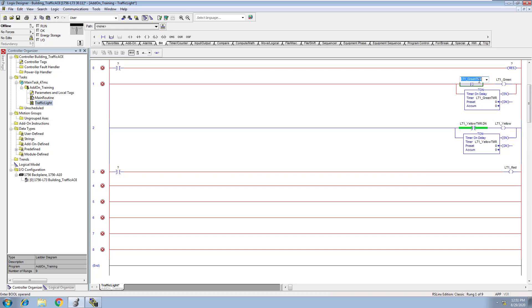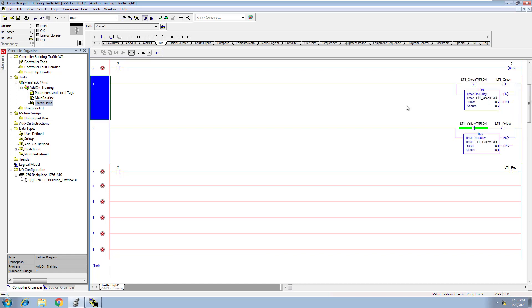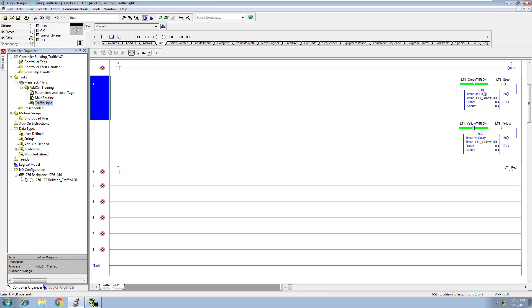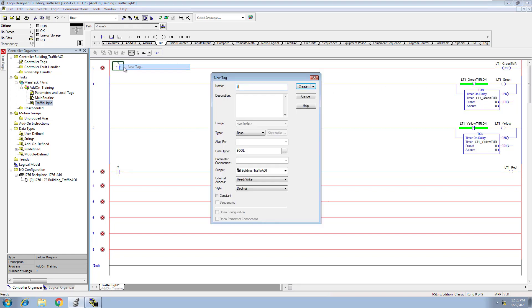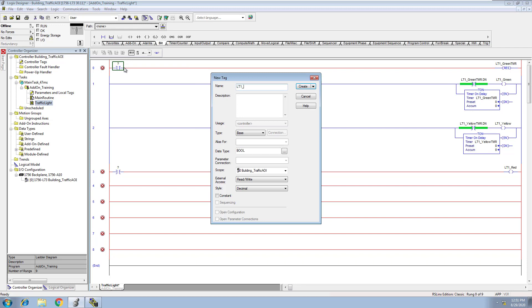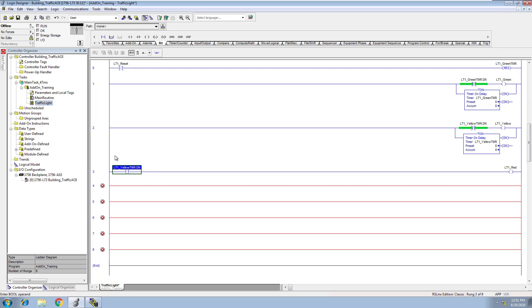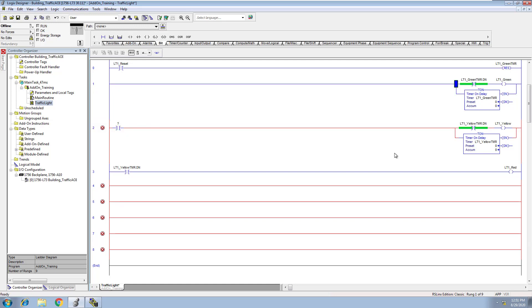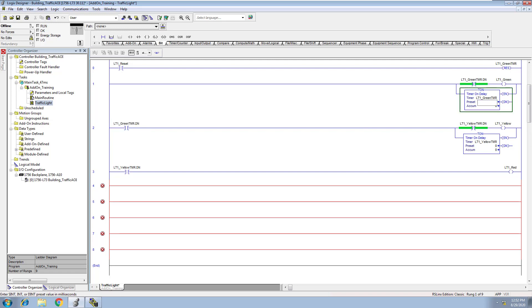First we want to build the logic. So when we're adding our timers, we're coming in here and adding everything. Now the reset we're going to do — this is going to be a reset for the very first one up here, and we'll call this LT1 Reset. We have our bit, and then we're going to drag this over. Our green light is going to come on automatically, and then when the green light is done based upon a timer — we'll put this as like 10 seconds — and then we'll put the yellow as like 3 seconds.